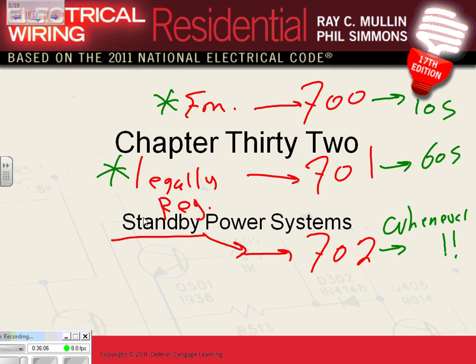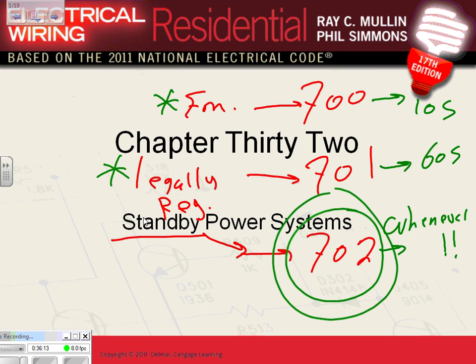Okay, so everybody knows the three articles that talk about it. We're talking about right in here. This is the one that we're talking about in this example, 702. The whenever. 700, 701, 702: 10 seconds, 60 seconds, whenever; emergency system, legally required, standby. Emergency, most of it, likely people's lives depend on it. Legally required, the government, be it state, federal, county or city government, decided that certain loads are very important for public safety or for whatever, and that becomes a legally required standby system. And it has to come up within 60 seconds. Any question, guys, about this? We'll talk about the other two systems later, but the most important one today is the standby power system.